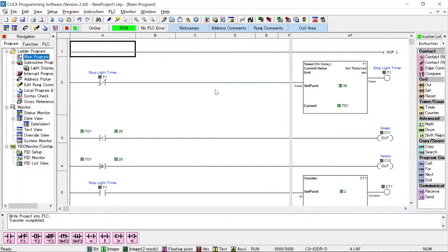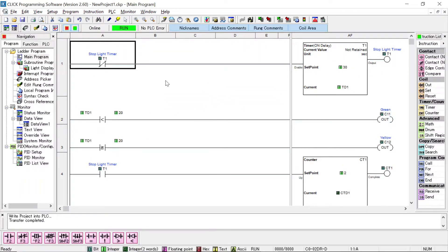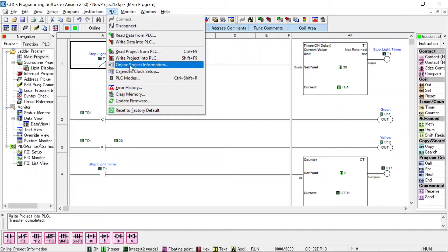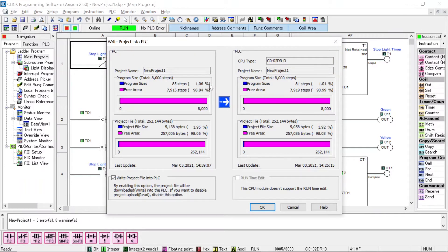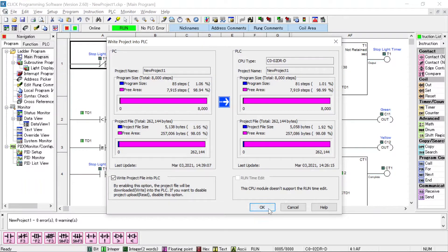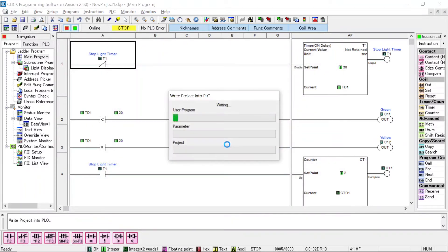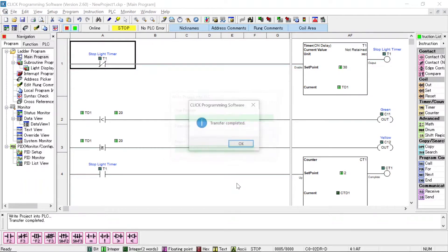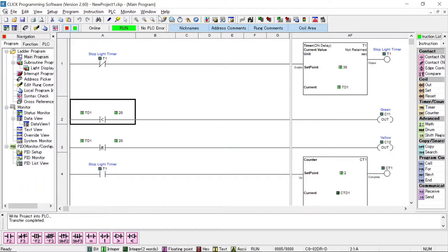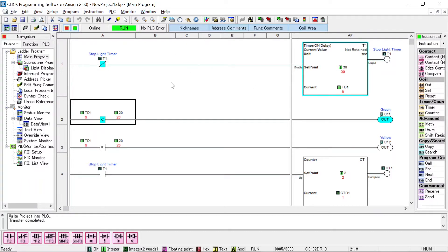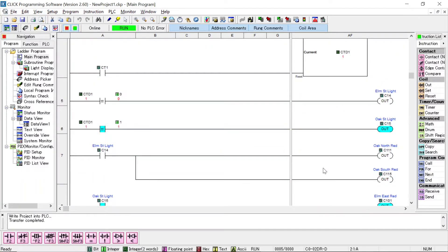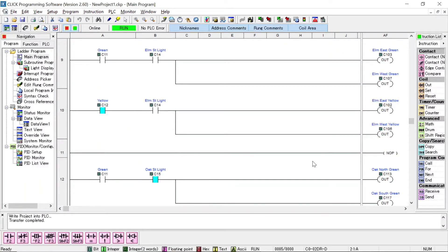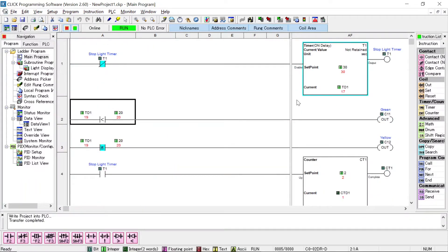Now then, in the main program, you see now the first thing I have is a no operation. I can take that out as well. So now then, I'm going to do a transfer, write project into the PLC. Down here, new project one, zero errors, zero warnings. Here you can see where this is what's in the computer. This is what's in the PLC CPU. So now I want to click OK. Yes, I have to stop. I'm going to go back, put it back in the monitor mode. So now we're monitoring. You can see my counter is up at the top now. It's continuing to count. It resets every 30 seconds.